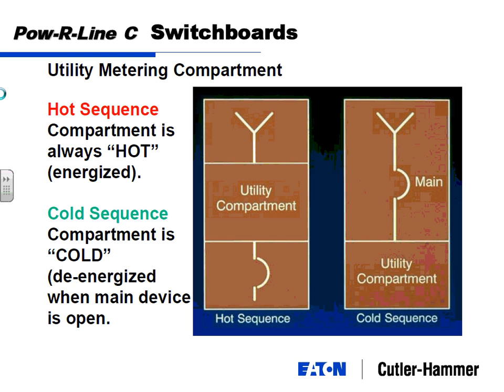One of the verbiage you'll hear is hot sequence and cold sequence, and what the heck do they mean for utility metering compartments? If the utility metering compartment is on the line side of the main breaker, it's called a hot sequence, because whether that breaker is open or closed, that utility compartment is always hot. If you swap those and put the main ahead of the utility compartment, it's called a cold sequence, because if you open that main, then that utility compartment is cold or dead. This doesn't fly anywhere up here, not in this neighborhood. This is what Xcel looks for.